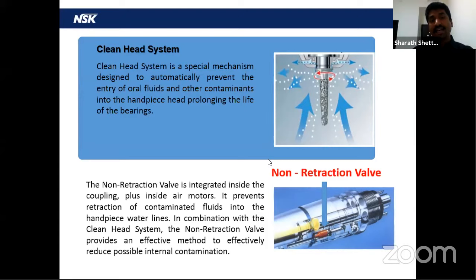This is taken care of by the clean head system from NSK, wherein we have a protective shield ahead of the head part of the handpiece. All the reverse flow which happens, the fluid particles, will enter back, but will hit the shield and go left and right, as you can see in the picture explaining the clean head system. That is what we call the clean head system. This mechanism is available with each and every handpiece of NSK. All the high-speed handpieces I'm talking about, the air rotor handpieces.